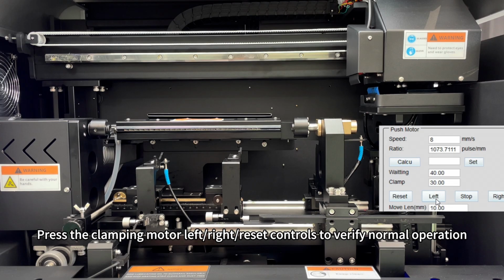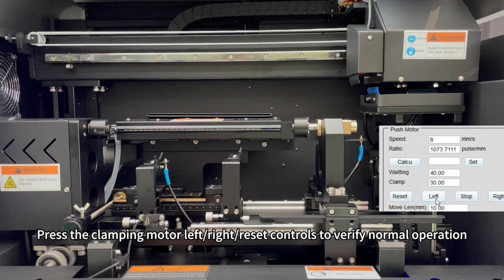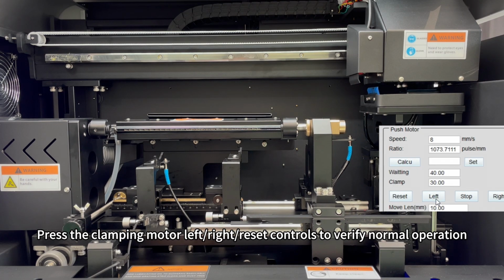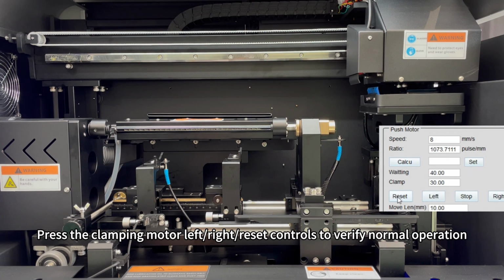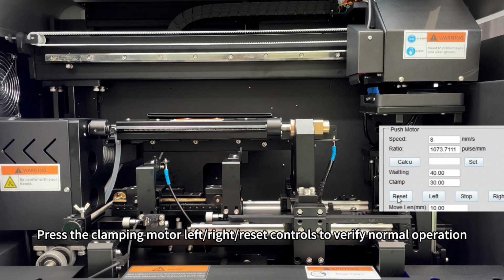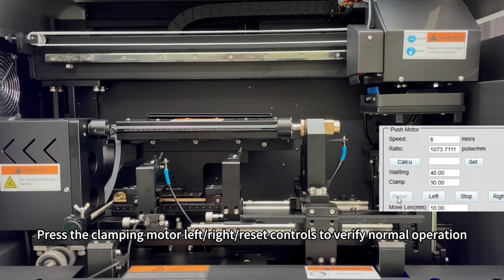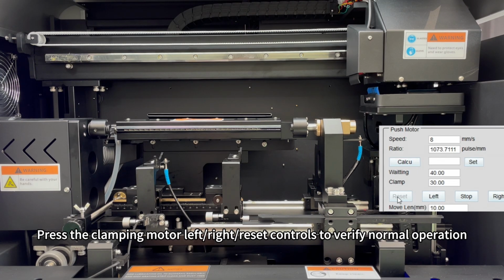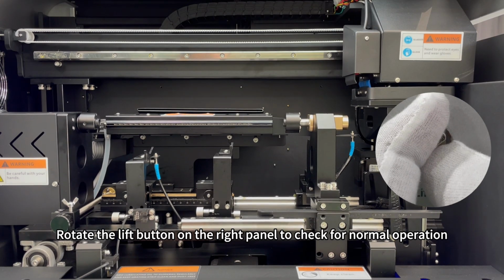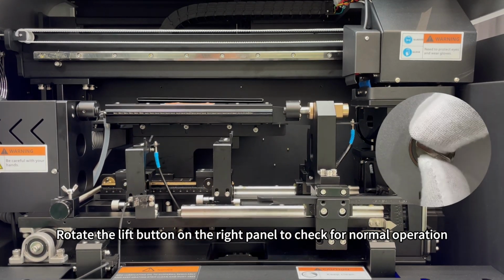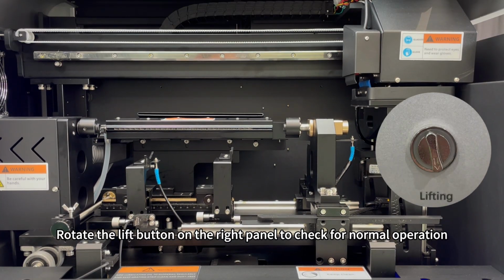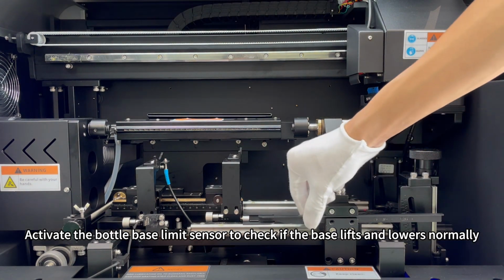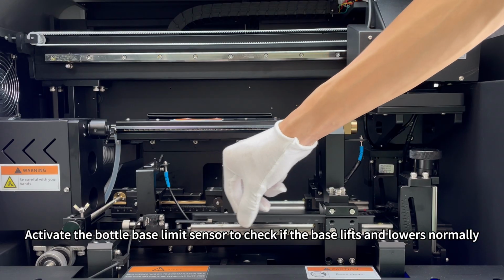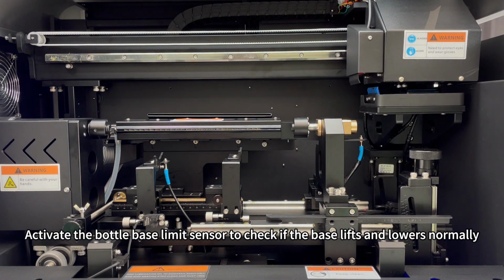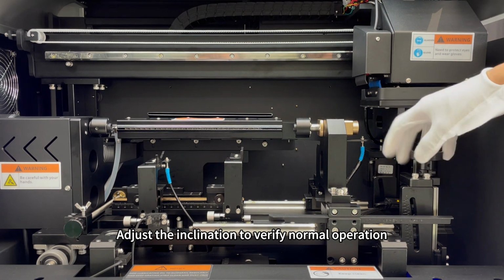Press the clamping motor left or right or reset controls to verify normal operation. Rotate the lift button on the right panel to check for normal operation. Activate the bottle base limit sensor to check if the base lifts and lowers normally. Adjust the inclination to verify normal operation.